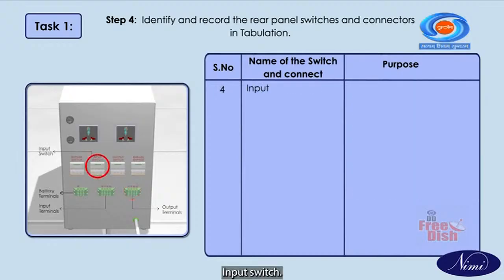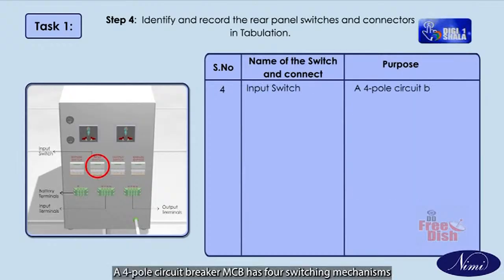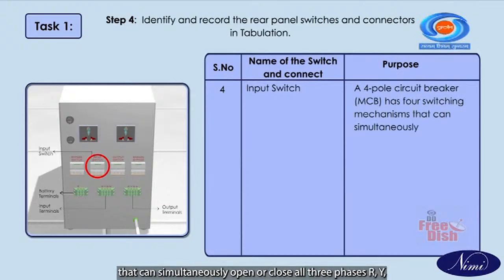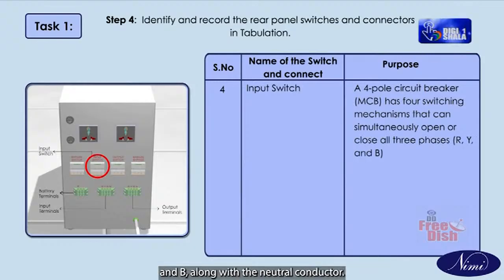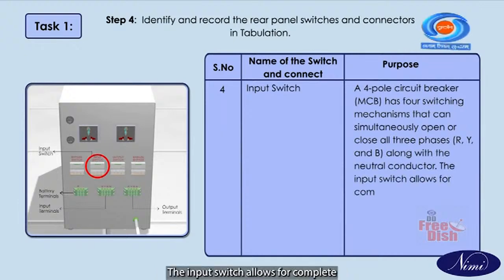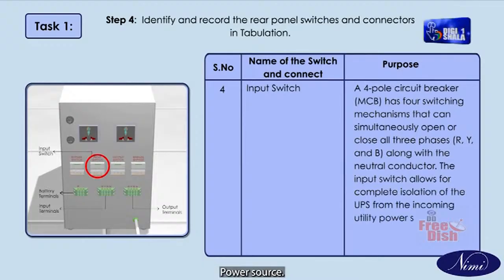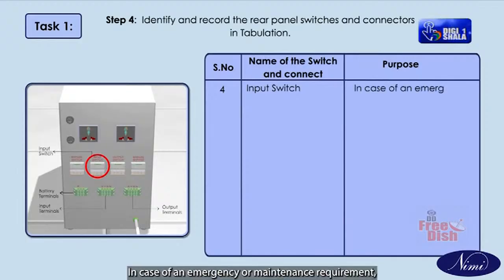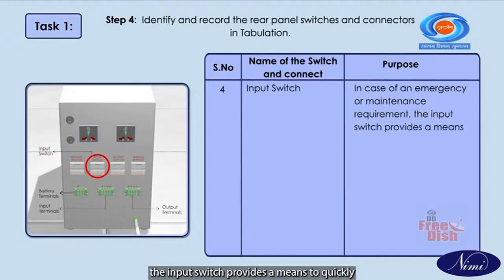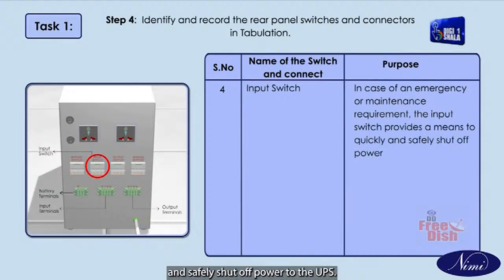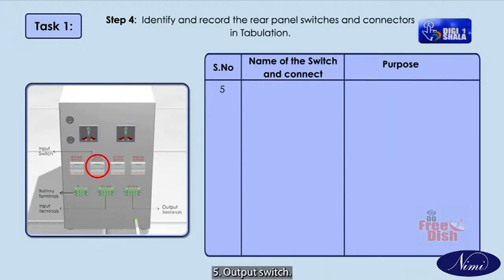Number 4. Input switch. A 4-pole circuit breaker MCB has 4 switching mechanisms that can simultaneously open or close all three phases R, Y and B, along with the neutral conductor. The input switch allows for complete isolation of the UPS from the incoming utility power source. In case of an emergency or maintenance requirement, the input switch provides a means to quickly and safely shut off power to the UPS.